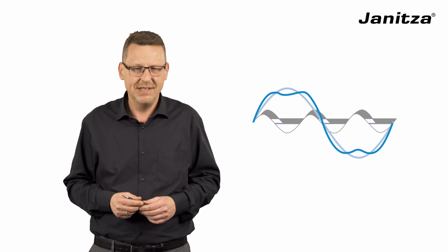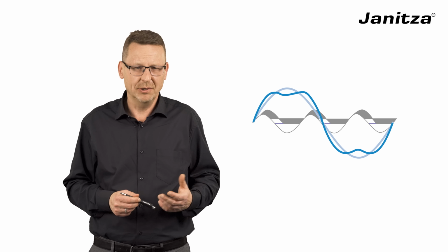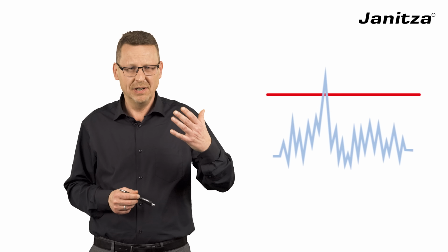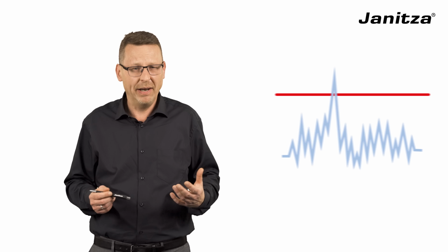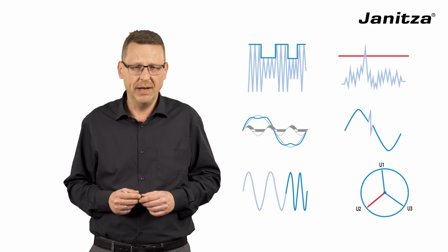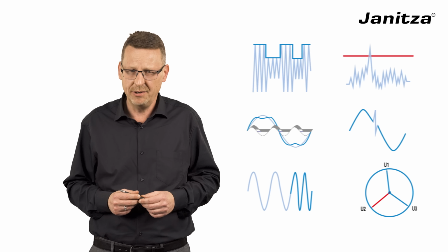Harmonics caused by VSDs can destroy different electronic equipment. Flicker, so when your screen is flickering. If you have an unbalanced system, that means one phase is much lower, that is caused by a single phase consumer. You have frequency deviations, and that comes from active in-feed converters like on the photovoltaic. And you have transients, which is mainly the reason why electronic equipment is really damaged. And be sure, those six categories of power quality issues can be mitigated, and our engineers would be very happy to help you.